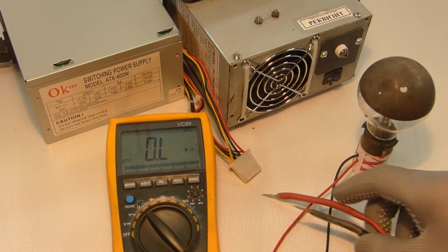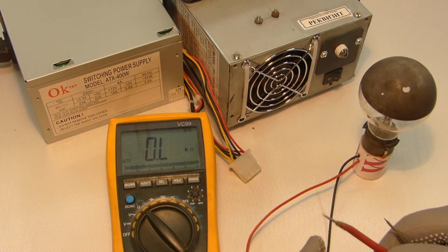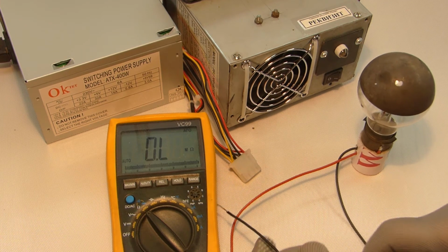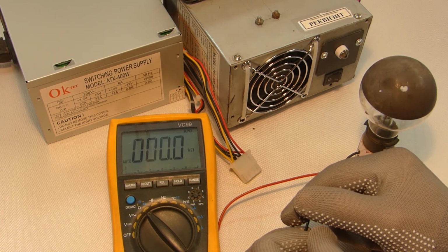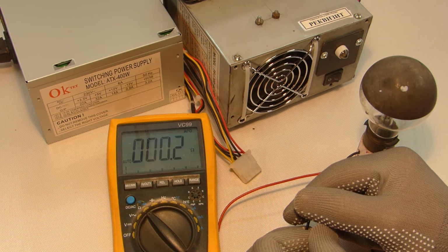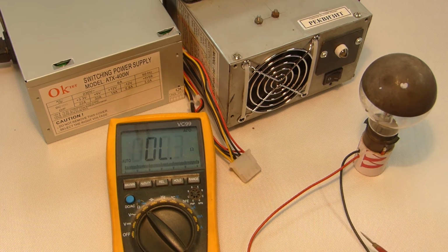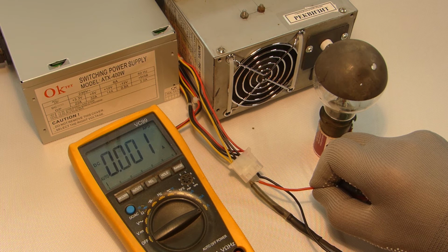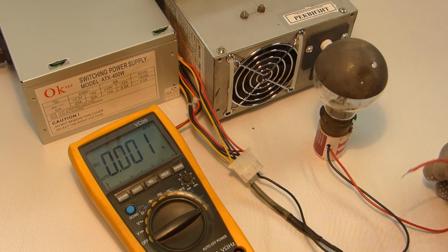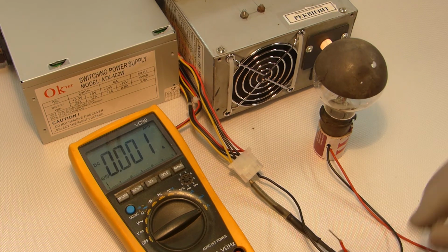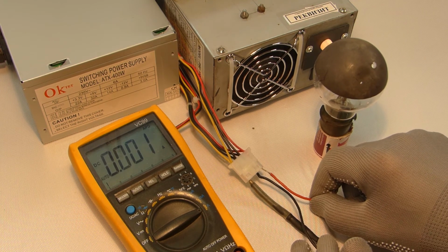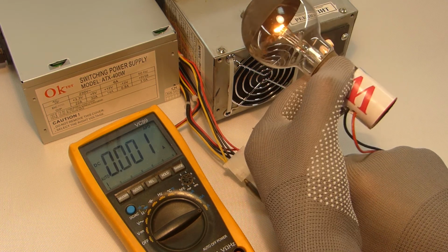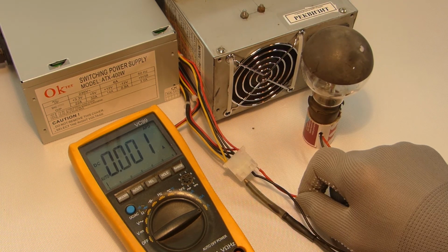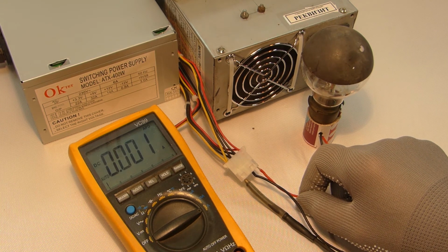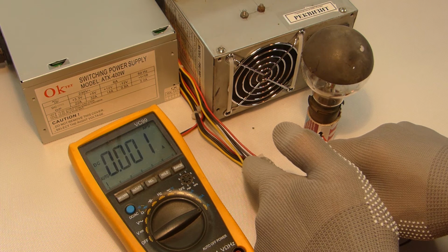Here is one thing I'd like to draw your attention to when using a powerful incandescent light bulb as an equivalent of load. This bulb is a nonlinear element and its resistance changes as the filament becomes warmer. When it's cold, it has a very low resistance, for example 0.3 ohm. That's why when you connect it to a 12-volt rail as an equivalent of load, the overcurrent protection element responds. But if you warm the filament inside the bulb with lower voltage, for example 5 volt, and then connect the bulb to a 12-volt rail, the PSU protection will not respond, as the filament has been heated and its resistance has increased.